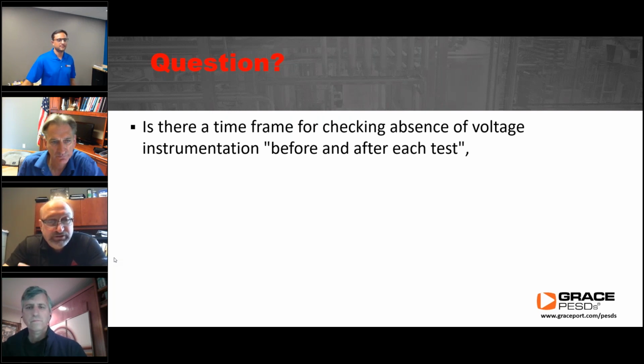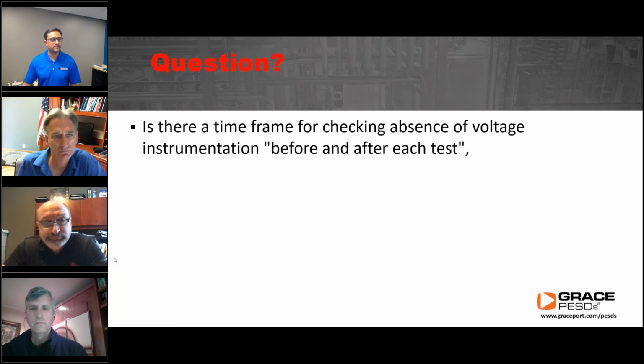I'm just reading these questions and trying to provide an answer, as we all are - really, that's what the practice, procedure, or policy would be when applying 70E or Z462. This is a component of establishing an electrically safe work condition: you do it right before any bare hand contact with exposed conductors and circuit parts, maintain that condition, and then re-energize the systems after finishing your de-energized repair, alteration, or other work. Any comments, John?